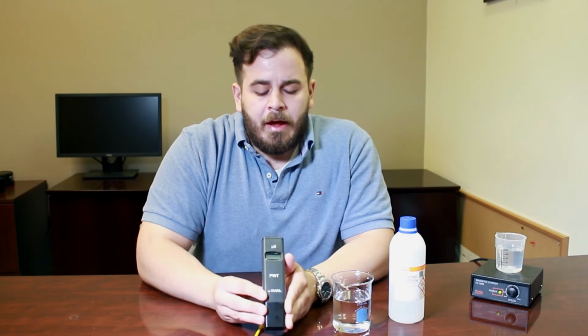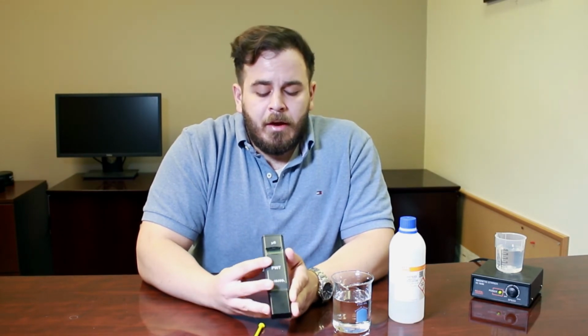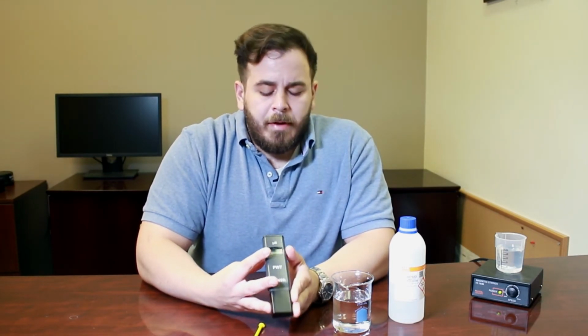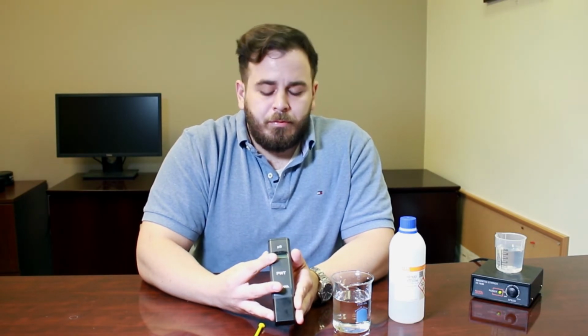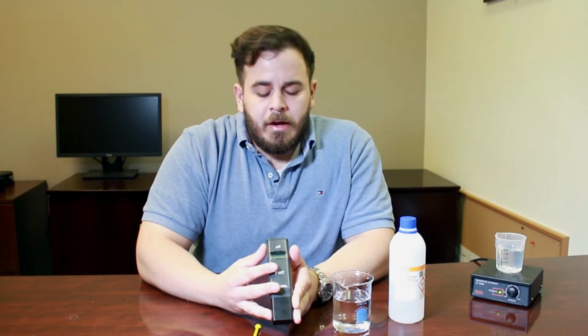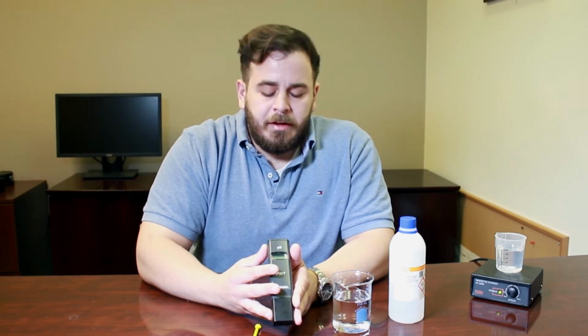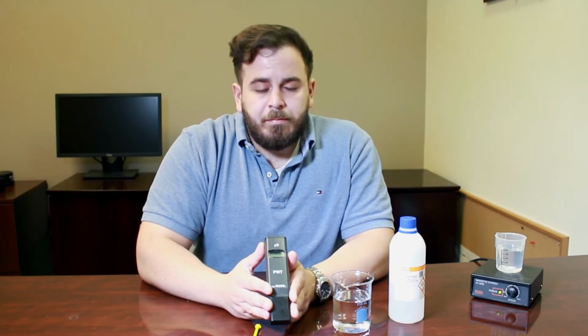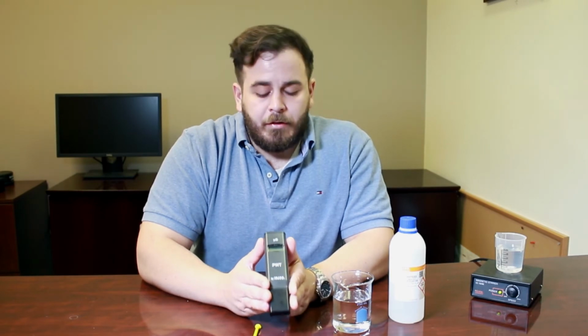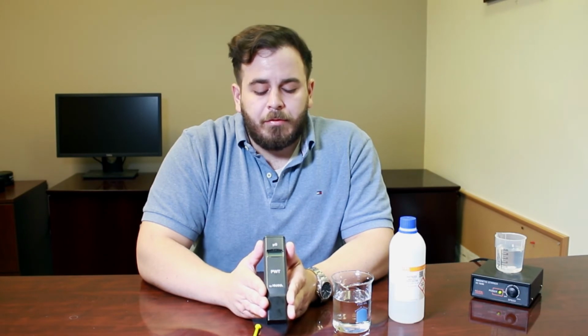Our HI98308 Pure Water Tester has an accuracy statement of plus or minus 2% of the full scale as well, but it's only designed to read from 0 to 99 microsiemens per centimeter. And that's an electrical conductivity measurement. That's pretty much a standard unit of measure for EC. And if we were going to convert that to TDS in parts per million, you'd use a conversion factor of 0.5, so it would roughly be about 50 ppm. So this is reading 0 to 50 ppm, which is 2% of full scale. So you're getting a much, much narrower accuracy statement for your TDS value.